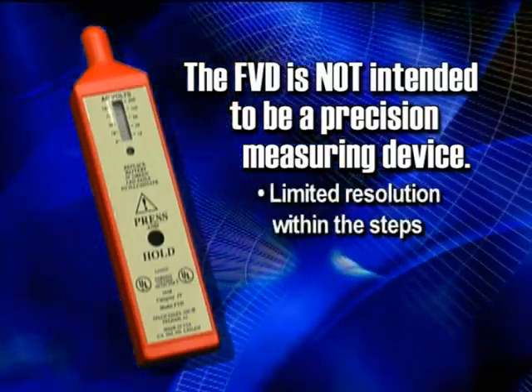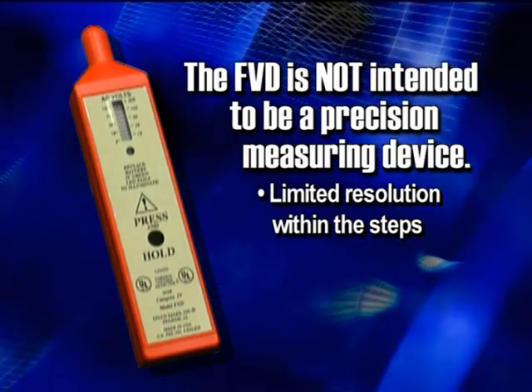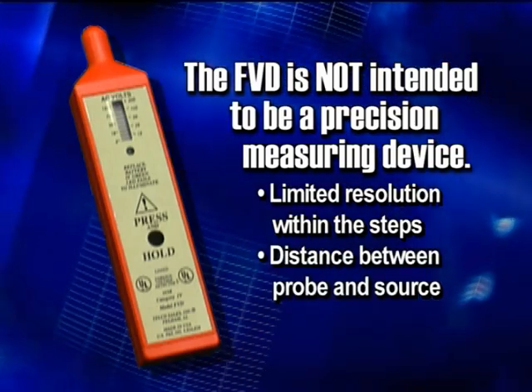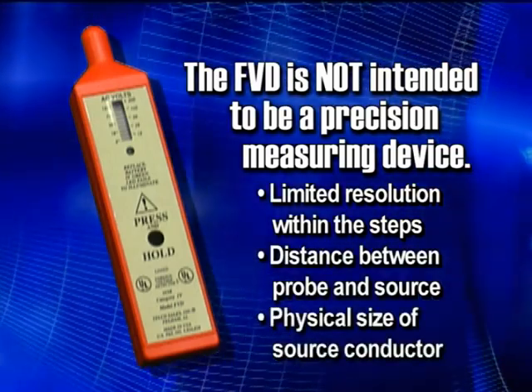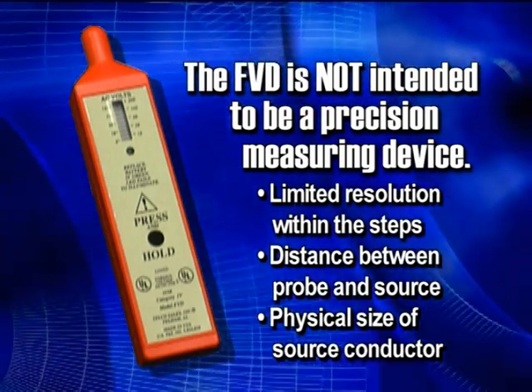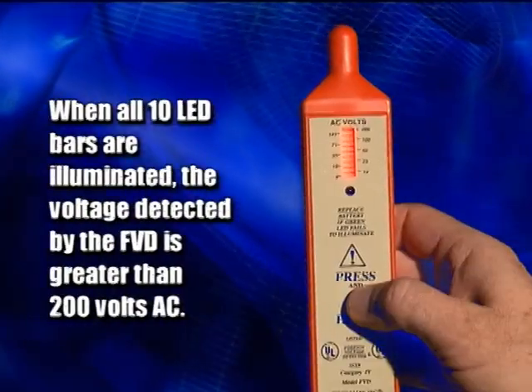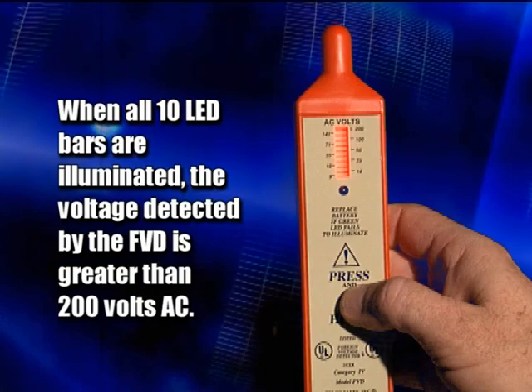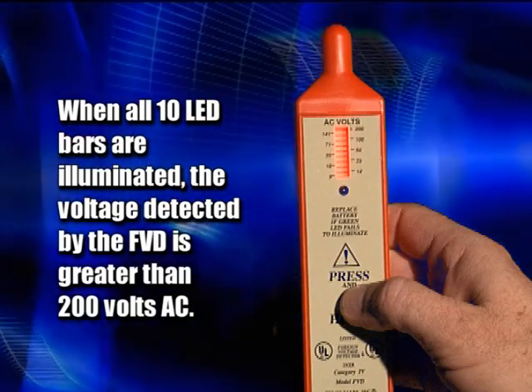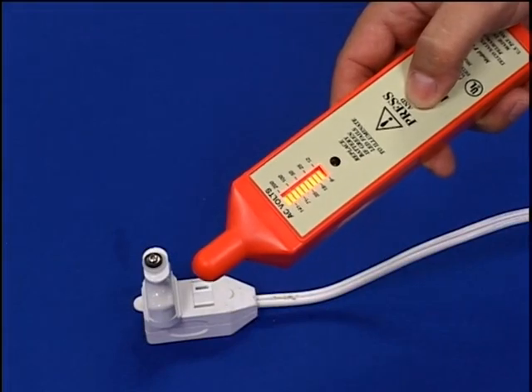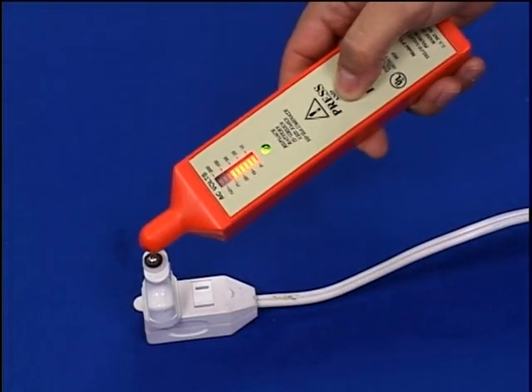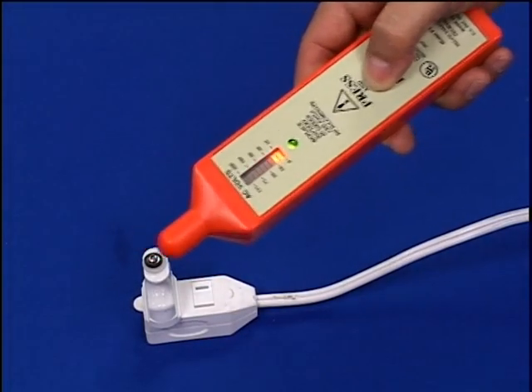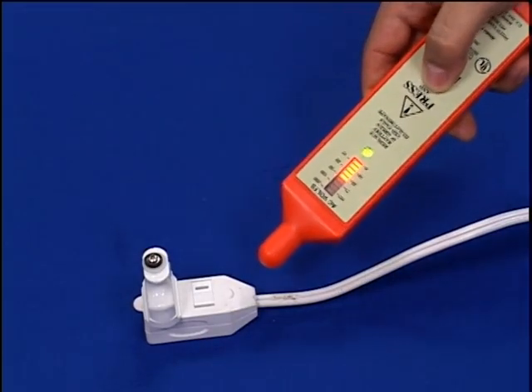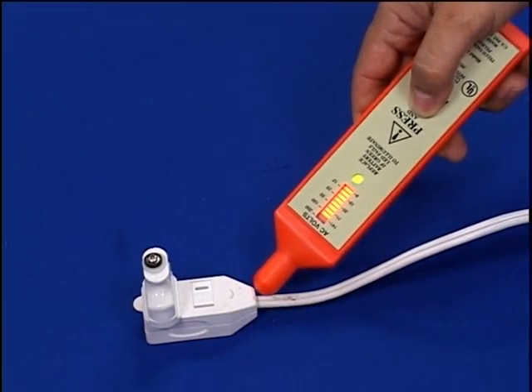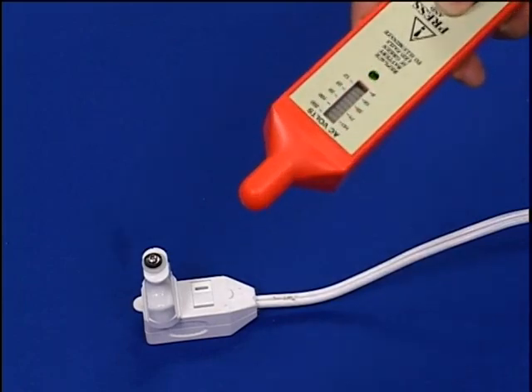Its precision is limited by the resolution within the steps, as well as the distance between the probe tip and the source, and the physical size of the source conductor. When all 10 bars are illuminated, the voltage detected by the FVD is greater than 200 volts AC. The FVD is calibrated so that the alarm will activate at 50 volts when the tip of the probe is against an energized source that is equivalent to a pair of 22-gauge insulated conductors.